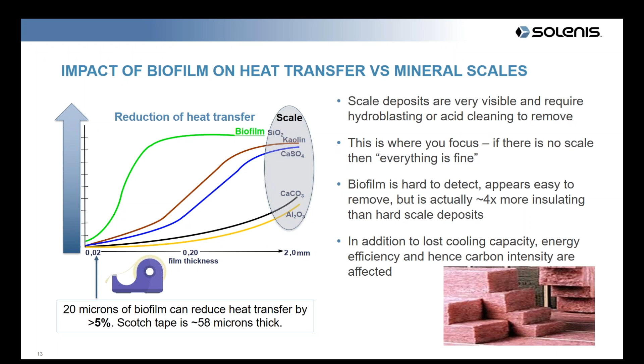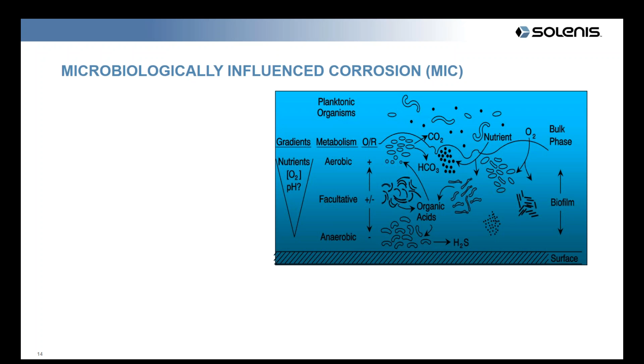To top that all off, these bugs can cause corrosion within your system. As you build up a layer, you can see the surface there, the system has oxygen in the water on the outside, and some of these bugs use oxygen for respiration, and we call those aerobic. As you get deeper into the system, some of the bacteria are what we call facultative. In other words, they can use oxygen, or they can live in an oxygen-depleted environment. But the really bad ones are right down there at the surface, where there is no oxygen left, and they use other things for their respiration.